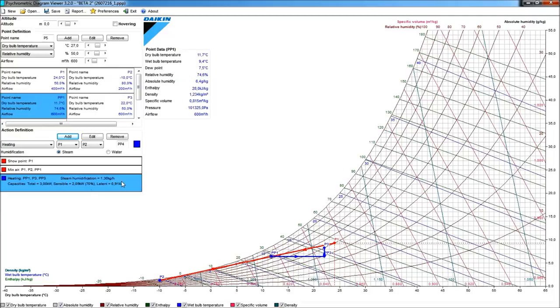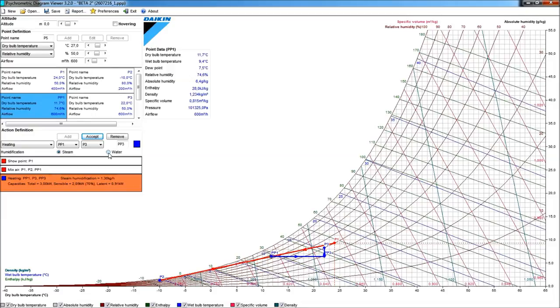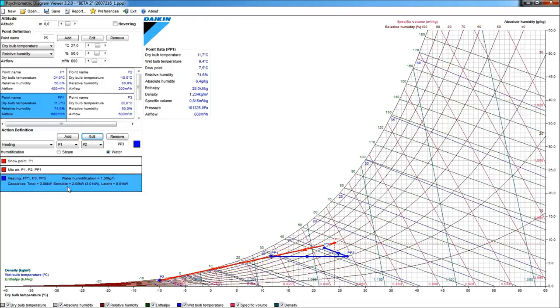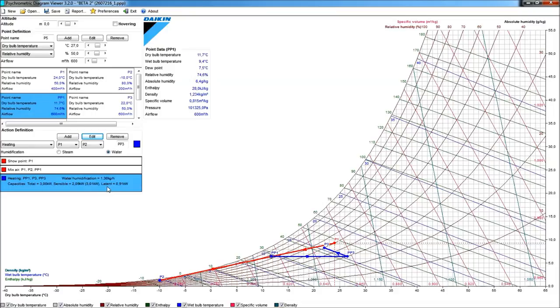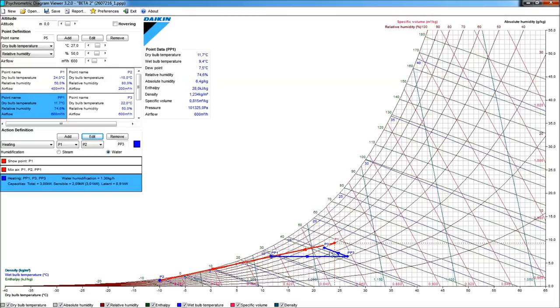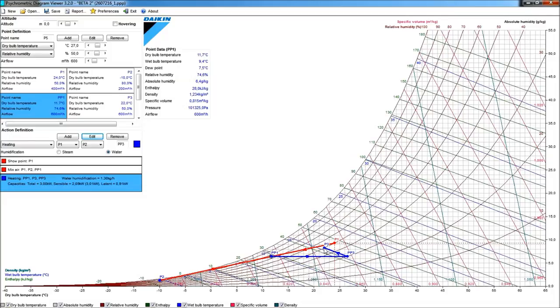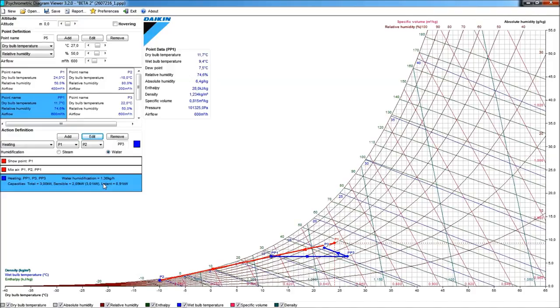If I would edit this action, so it's still highlighted, I can edit it, I see that I could change from steam, instead of steam use water, and there it becomes completely different, because there we would see, when I accept this here, that we would use a total heat still of 3 kW, out of which 2.09 kW would be sensible, and the same 910 W. But we see that in reality, we would have to heat with 3.01 kW, because part of that heat will be used to evaporate that water to reach point P3. You see that we are following here the lines of constant enthalpy, so we will evaporate that water and we will reach point P3. That evaporation again, or the amount of moisture that we need, will still be the 1.3 kg per hour that we will have to add.